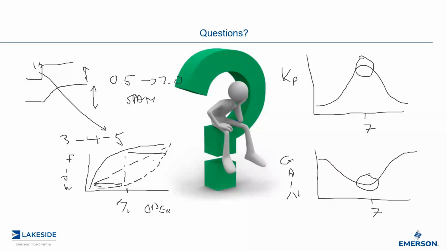It's a Band-Aid solution, done temporarily while they buy a new feed water pump. It's a very large pump with a 52-week delivery. When they do put the new pump in, we will have to take that characterizer out.